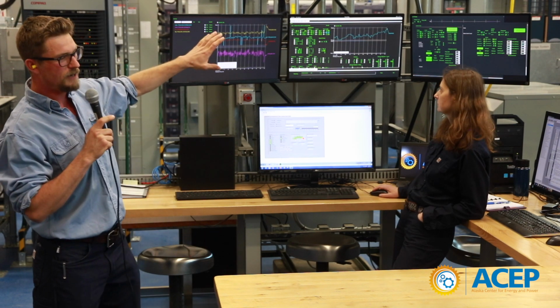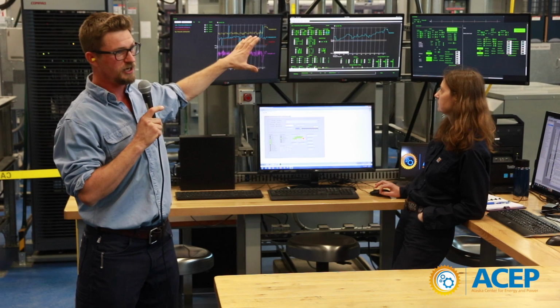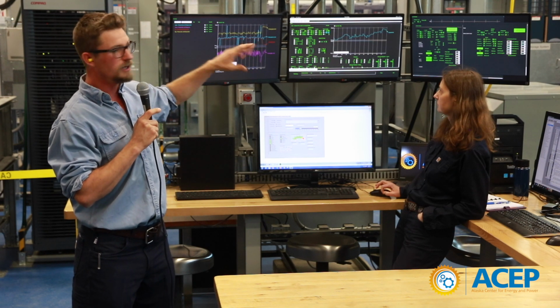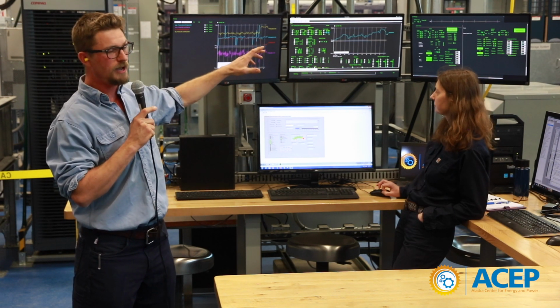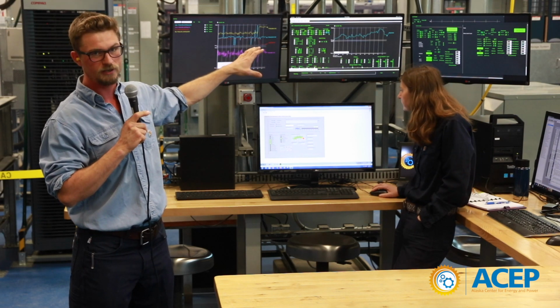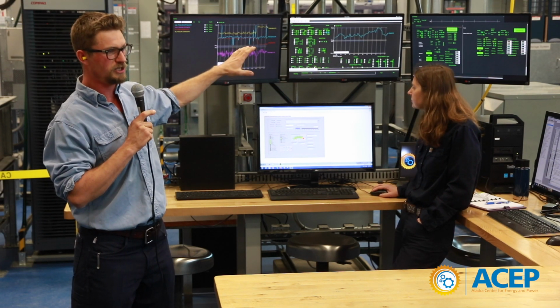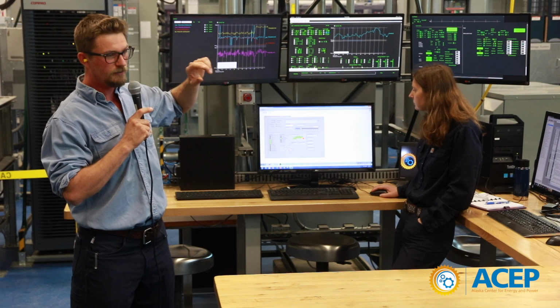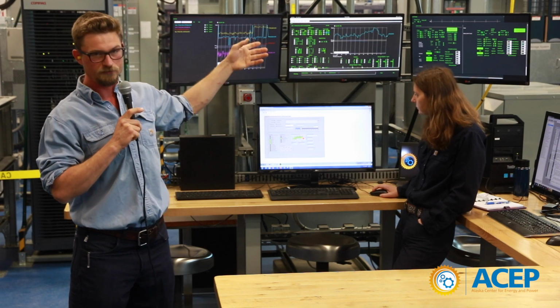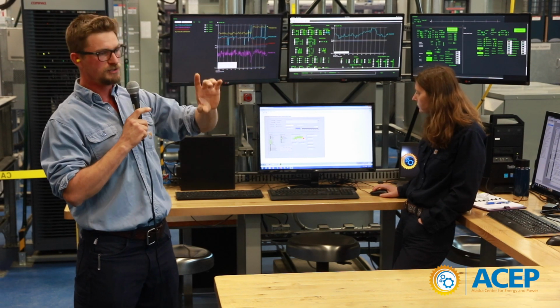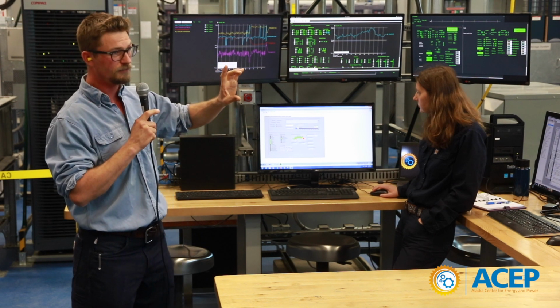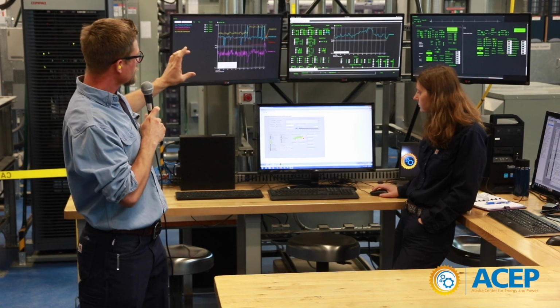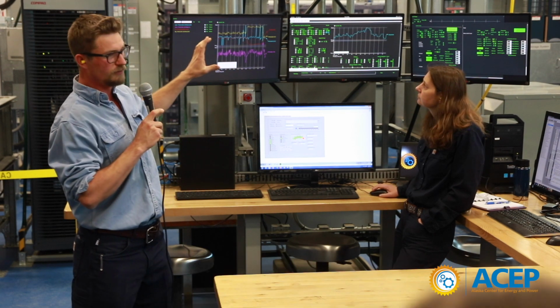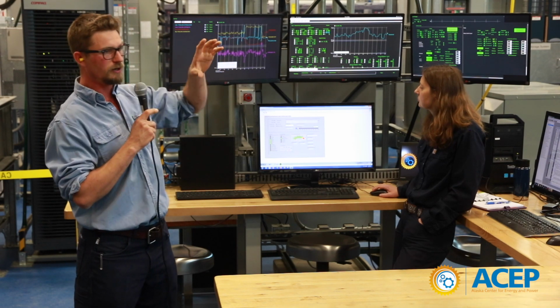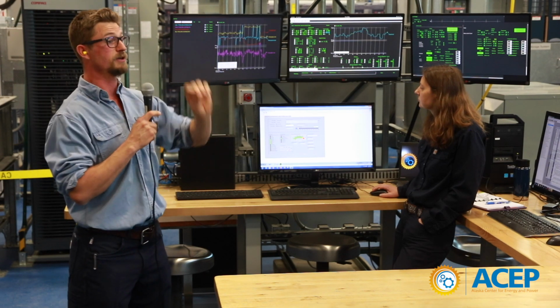So far we've been having to run the same size generator all the time, no matter how much wind power we put on the grid. The generator, as long as it's running, is consuming fuel, and it has to keep a certain loading on it. So in order to save fuel, you want to run a smaller generator, or turn that generator off.